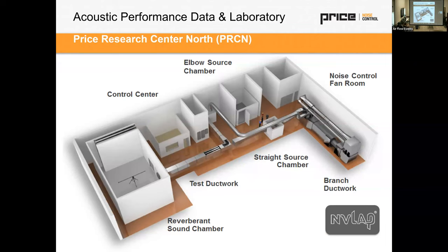A reverberant chamber has all hard surfaces — eight-inch thick concrete — in a large box, allowing sound to dissipate and be measured over time using a rotating boom microphone. From this, insertion loss, sound pressure, and sound power are accurately calculated. The opposite is an anechoic chamber, which is completely absorptive with no echo — so quiet that occupants can hear their own heartbeat.